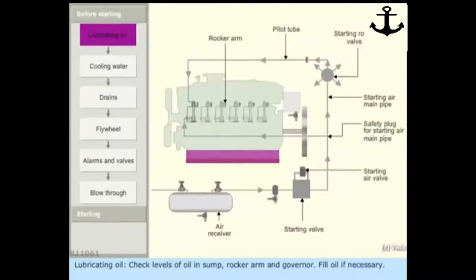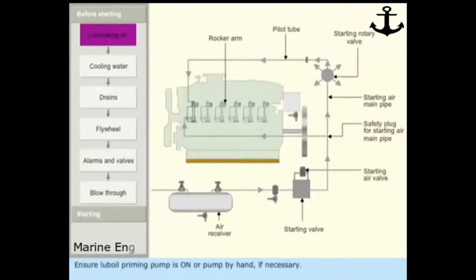Lubricating oil: Check levels of oil in sump, rocker arm, and governor. Fill oil if necessary. Ensure lube oil priming pump is on or pump by hand if necessary.